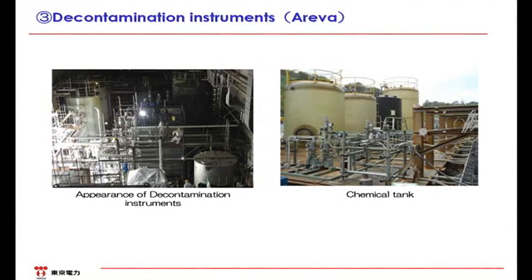The next slide shows Areva's decontamination instrument. Cesium is adsorbed by zeolite in the cesium adsorption tower. Areva's decontamination instrument coagulates cesium and other radioactive materials dissolved into the water using chemical reactions. The picture on the right side shows tanks for the chemicals necessary for the treatment. The chemicals are injected from these tanks into the decontamination instrument for coagulation. Although the decontamination index of Areva's is high, it generates waste sludge. Therefore, we have stopped using it and it is now on standby.